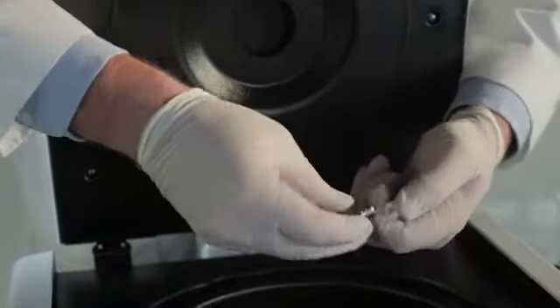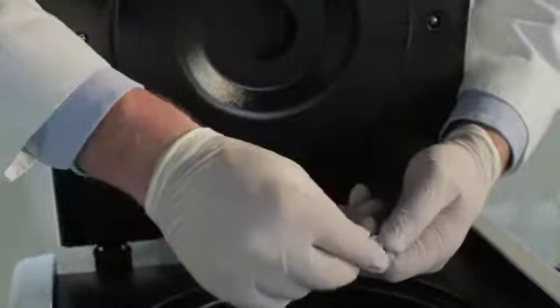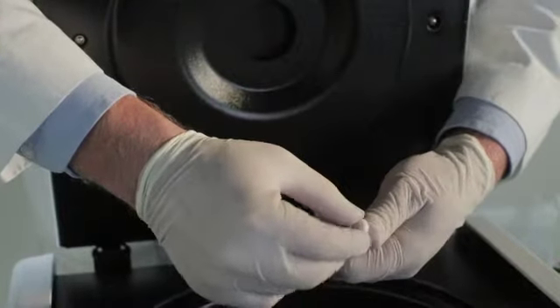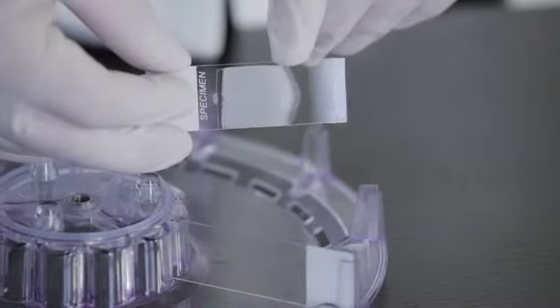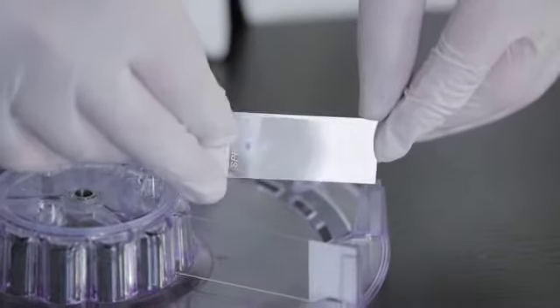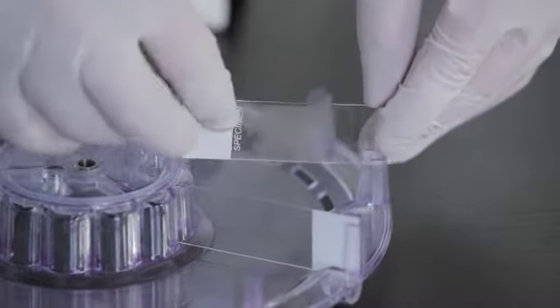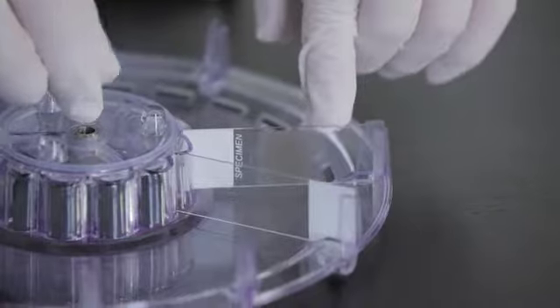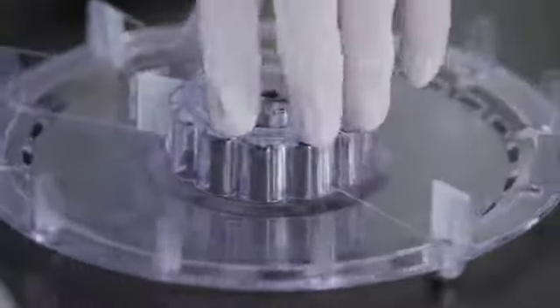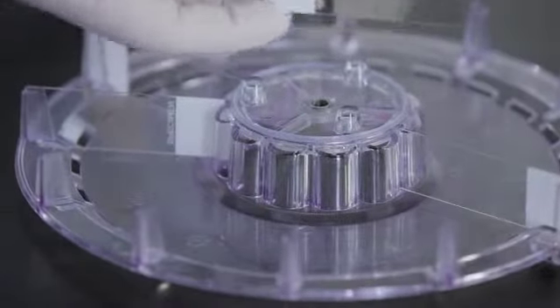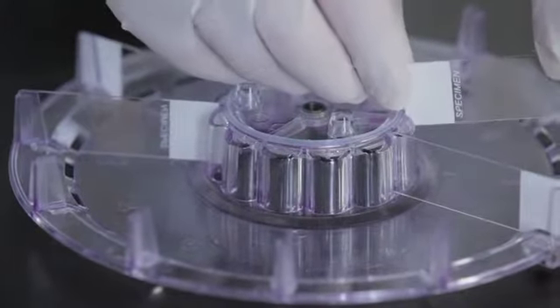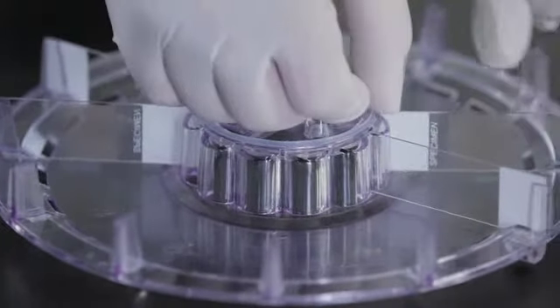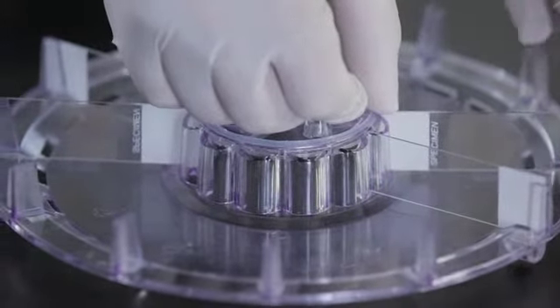This insert is required so that the A, B, and C stains are mixed properly before they're applied to the microscope slide. The Hematology Pro Stainer uses the 12-slide carousel, and it is important that the slides are loaded so that the feathered edge of the blood smear is pointed towards the outside of the carousel. Airflow across the face of the slide is a requirement for proper staining. The best staining occurs in this area of the slide.